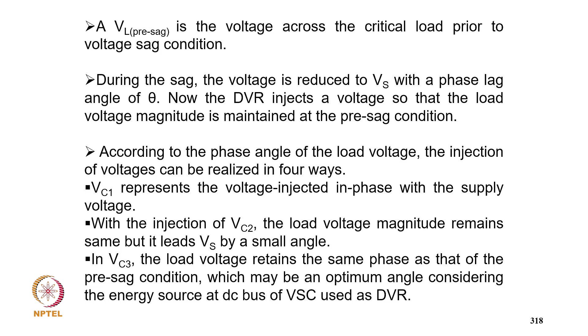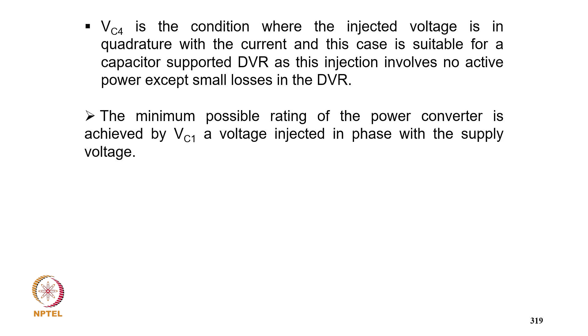So VC4 is the condition where the injected voltage is in quadrature with the current, and this case is suitable for a capacitor supported DVR. This injection involves no active power except small losses in the DVR. A minimum possible rating of the power converter is achieved by VC1, a voltage injected in phase with the supply voltage. Now coming to analysis and design of DVR.